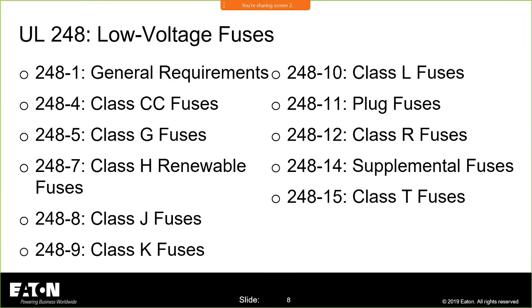If I look at UL 248, I have .1 as general requirements, very similar to the NEC. They'll have general requirements that apply generally. And then there are specifics for each of the classes of fuses, because each of these fuses will have different sizes, different types of rejection features, and different performance capabilities. How we test these, we establish in 248, all of the criteria that these fuses need to pass. This is not meant to be a UL standard educational class, but this is basically to let you know that UL 248 is the standard. And if you see a 248-5 or -12, those are the specific classes of fuses.